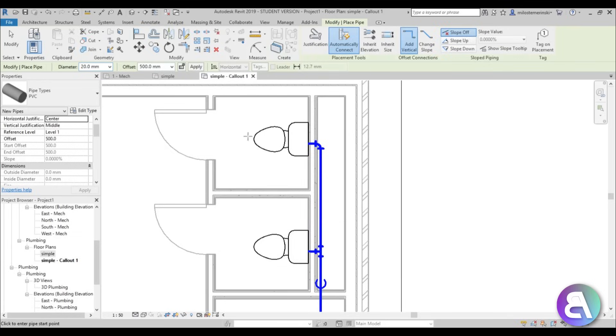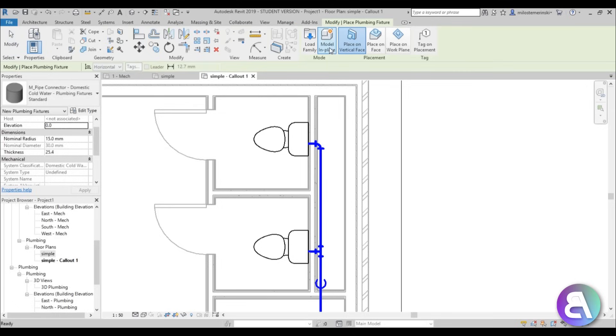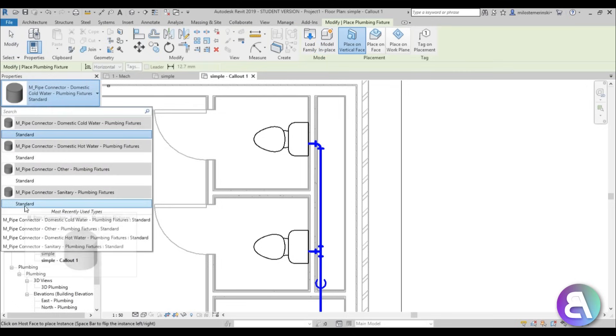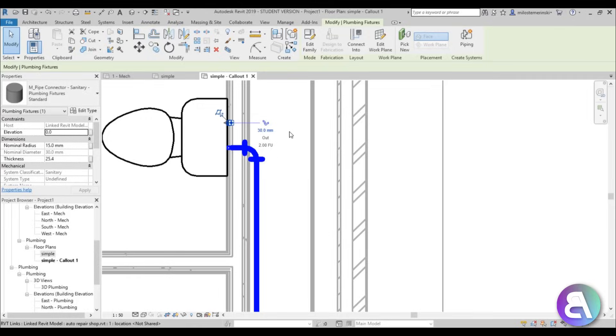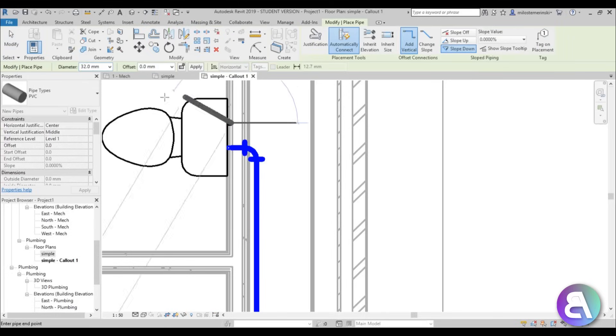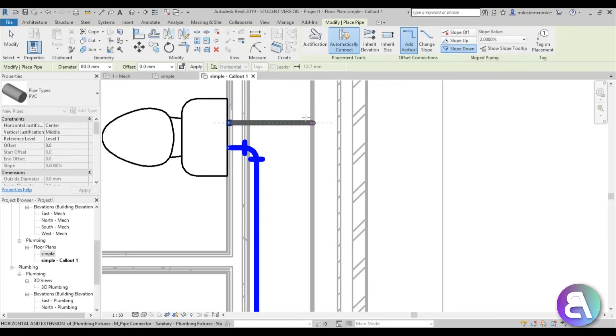Before placing the PVC pipe, place a sanitary connector. Go to Plumbing Fixtures, search for the Sanitary Standard connector, and place it on the wall just as before. Set its elevation to zero (compared to 500 mm for the supply connector). Then select the Pipe tool, change the diameter to 80 mm, and before drawing, change Slope from Off to Slope Down and set the value to 2% (or your local standard).